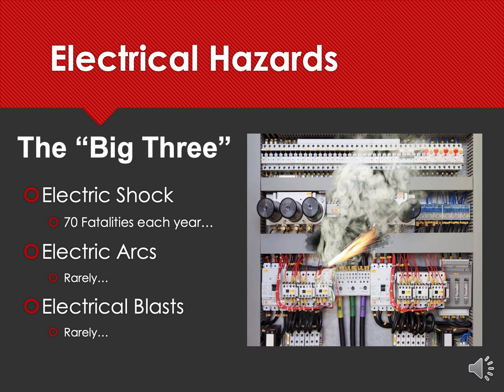Having said that, electrical arcs and electrical blasts have a lot to do with the capacity of the system, and in this case, those small wires do matter. So on this particular panel, there is not a significant arc flash hazard, except if you look at the picture in the very bottom center, where you'll see three colors, yellow, green, and purple. Those conductors coming into the panel might have enough capacity to precipitate a significant arc flash.